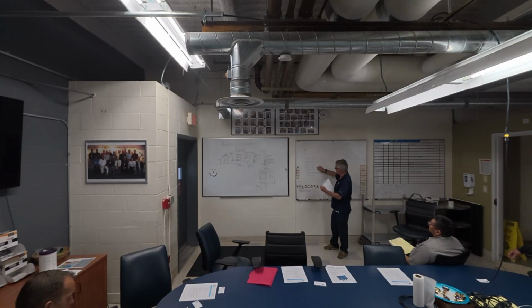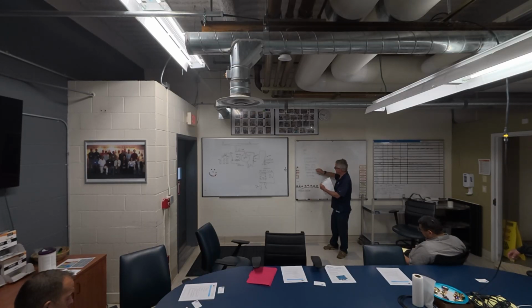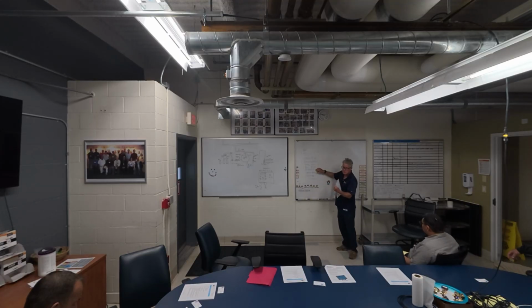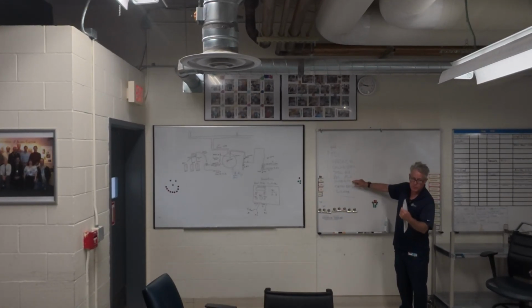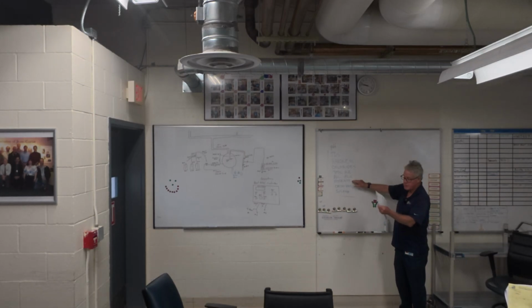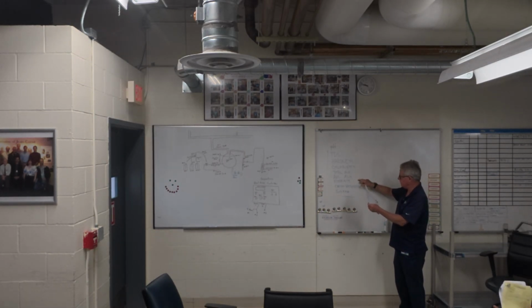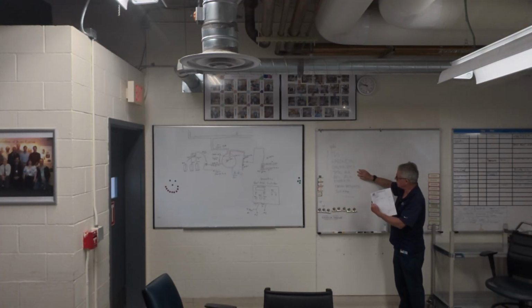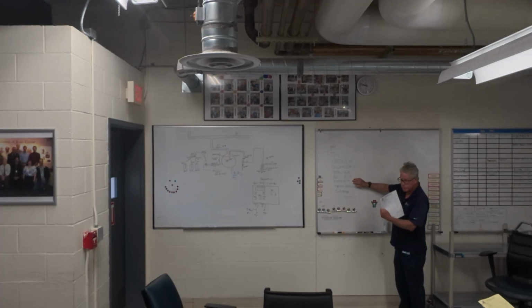Alkalinity is part of the equation too, though it's not as important since we're mostly looking at hydrate alkalinity. This tells us the percentage or amount of our chemical that's in each boiler -- whether we have enough. We're trying to hit a range between 120 and 190, with 200 still in range. This is all part of a formula; you don't really need to know the details, though we can get into it if you want. Mainly, we're focusing on hydrate alkalinity.